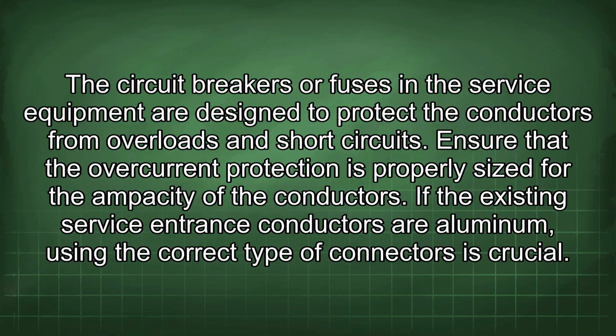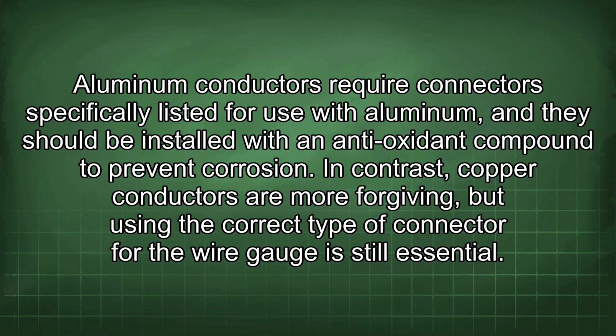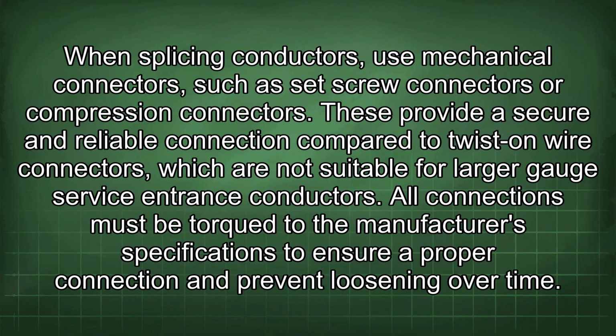If the existing service entrance conductors are aluminum, using the correct type of connectors is crucial. Aluminum conductors require connectors specifically listed for use with aluminum, and they should be installed with an antioxidant compound to prevent corrosion. In contrast, copper conductors are more forgiving, but using the correct type of connector for the wire gauge is still essential. When splicing conductors, use mechanical connectors such as set screw connectors or compression connectors. These provide a secure and reliable connection compared to twist-on wire connectors, which are not suitable for larger gauge service entrance conductors. All connections must be torqued to the manufacturer's specifications to ensure a proper connection and prevent loosening over time.